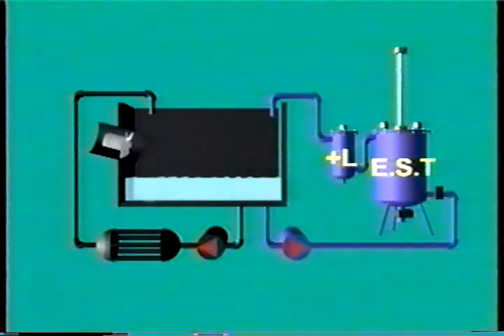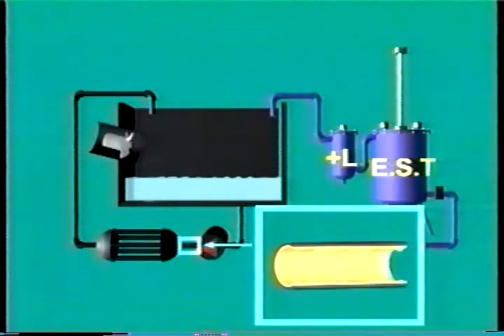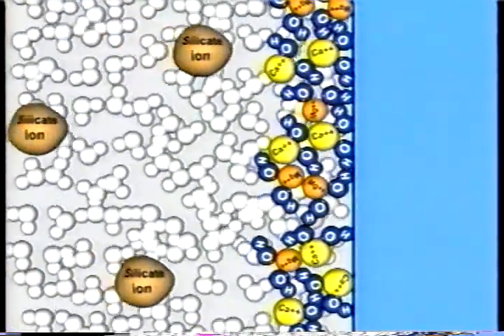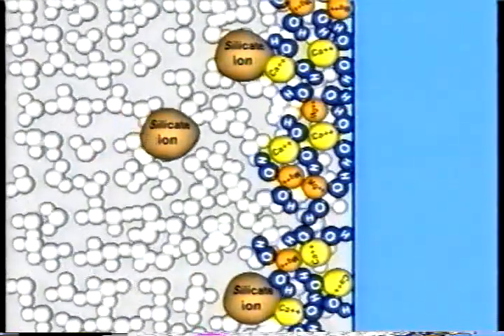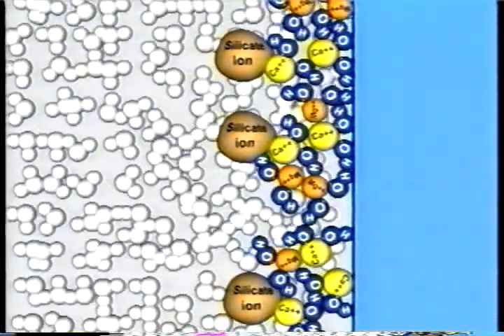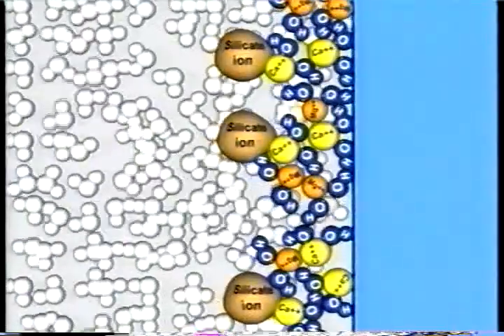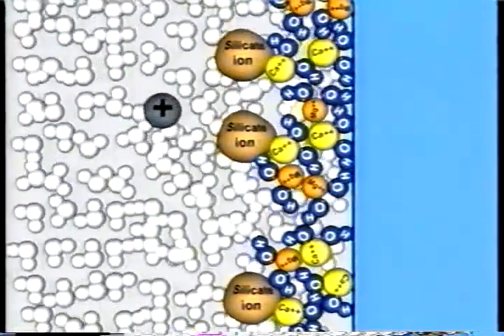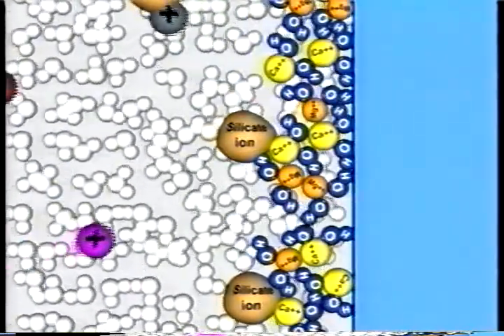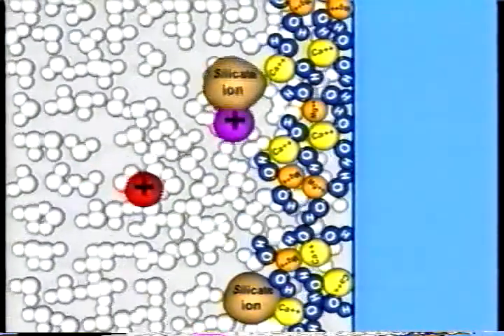In water systems with high level of silica, such as in cooling towers, it is recommended that the EST system be equipped with the electrolysis plus L system, which prevents crystallization of silica and the scale remaining in the water. Silica originates in dust from the air that settles in the cooling towers, and together with calcium in the water, forms hard, insoluble sediment that clogs the pipes. The plus L system employs a special electrode that releases into the water flowing through it highly soluble metal ions with strong positive charges, which prevent crystallization of silica and scale in the water.